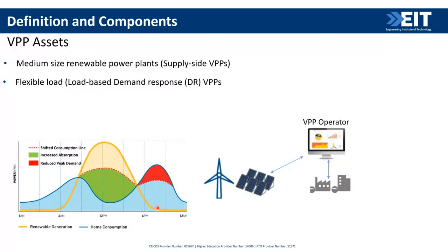You can see that around 9 p.m. here, the load demand is on peak. Now, during this time, the power generation may not be enough for feeding the load in some days. So in that situation, the flexible load gets turned off to reduce the load. So when they are off, the load curve will decrease by this much that you can see in red color.